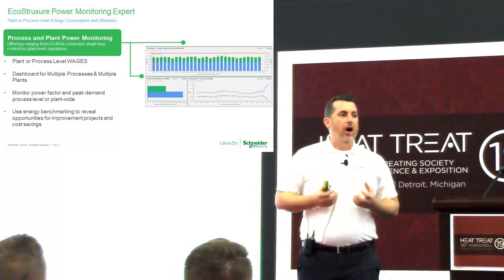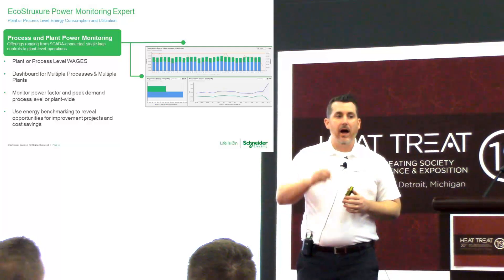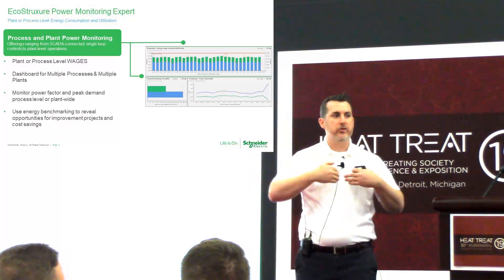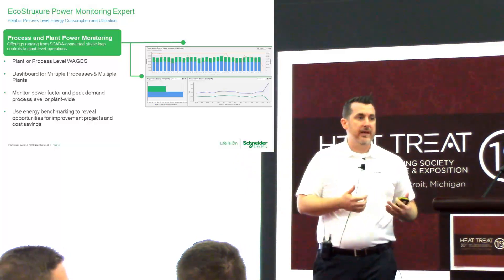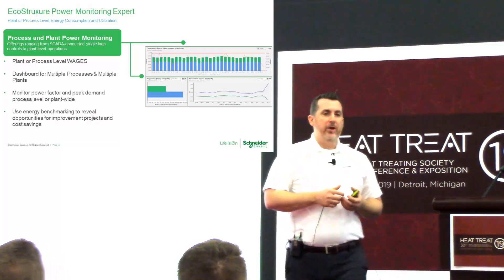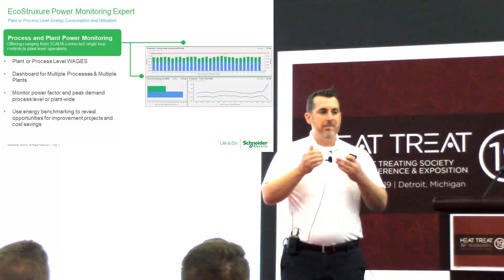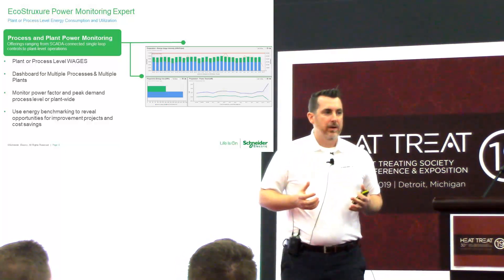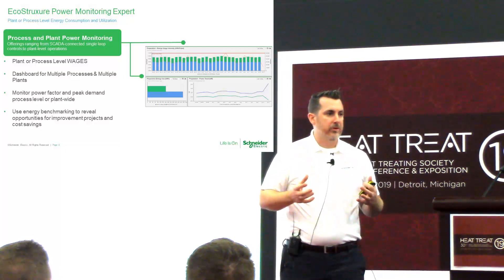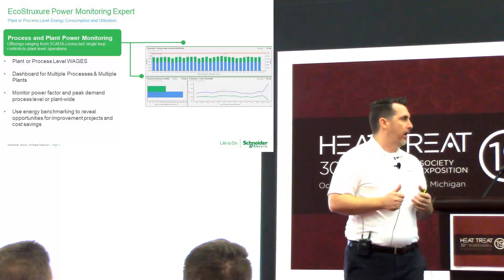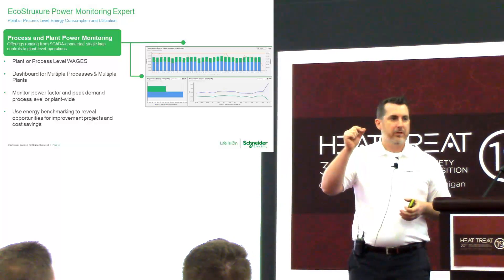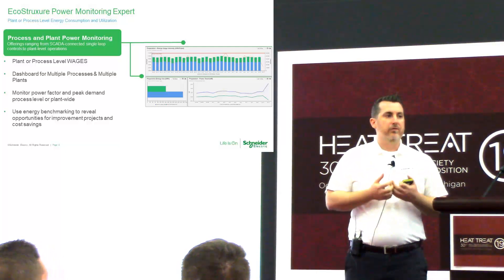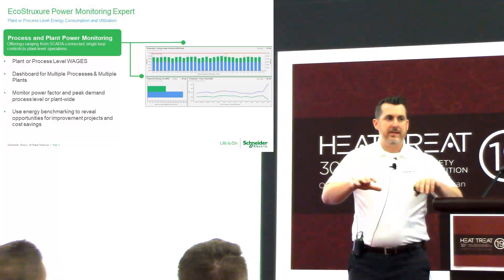We have the ability to offer power factor monitoring not just at the process level, but across the whole plant — the entire distribution chain leading to that heat treat or production asset. We also have the ability to monitor peak demand levels within a plant. If you're in an energy-intensive production environment with peak demand caps from your utility, we can monitor and provide insights into that on both a process level and a plant level.